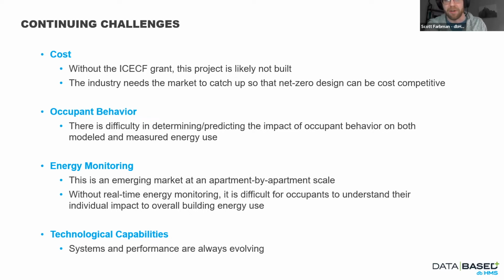As I noted, occupant behavior, there's a lot of variability there. So we're doing our best to capture that. Tom ran a series of sensitivity analyses and iterations that said, let's see what happens if we have another year of COVID and everyone's working from home and we jack up the plug loads and miscellaneous electrical loads times whatever. And then let's make sure we're including that in some of our annual projections on solar to make sure we don't get bit in the butt later down the road. And that's a really interesting component of this whole project. It's not just about the building design, but it's about predicting the future in worst case scenario.